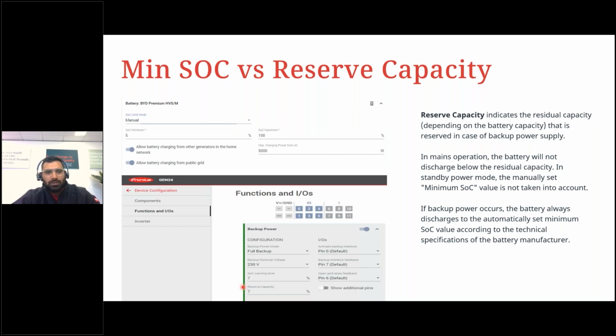So when you have set the reserve capacity, for example, to 20%, in grid connected mode, the inverter or the battery will not go below this 20%. And in off-grid mode, we will go down to whatever is the minimum SOC possible for the battery. So if you wanted to reserve some battery power just to be used in backup scenarios, because you have quite often blackouts, you can set this reserve capacity to a higher value. By default, normally they're coming at 7% when you set the SOCs to automatic mode. But of course, you can change all these values.